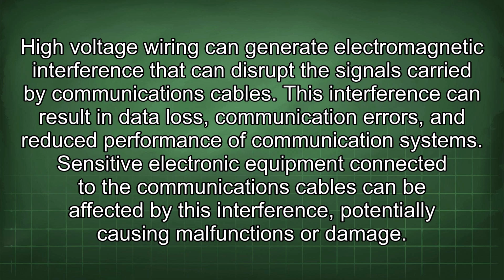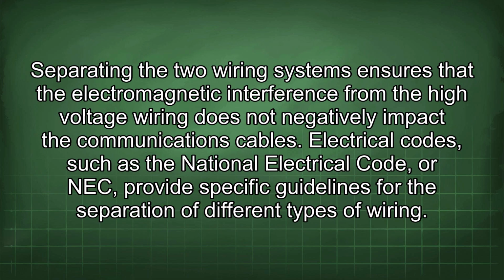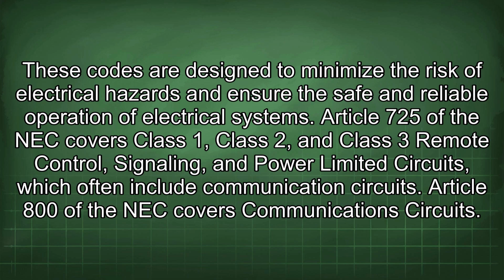Sensitive electronic equipment connected to the communications cables can be affected by this interference, potentially causing malfunctions or damage. Separating the two wiring systems ensures that the electromagnetic interference from the high voltage wiring does not negatively impact the communications cables. Electrical codes, such as the National Electrical Code, or NEC, provide specific guidelines for the separation of different types of wiring. These codes are designed to minimize the risk of electrical hazards and ensure the safe and reliable operation of electrical systems. Article 725 of the NEC covers Class 1, Class 2, and Class 3 remote control, signaling, and power-limited circuits, which often include communication circuits.